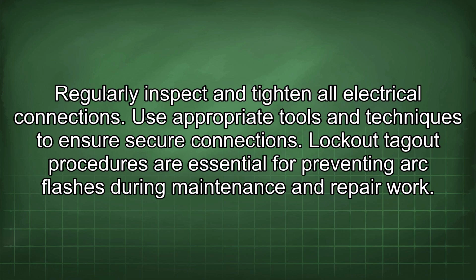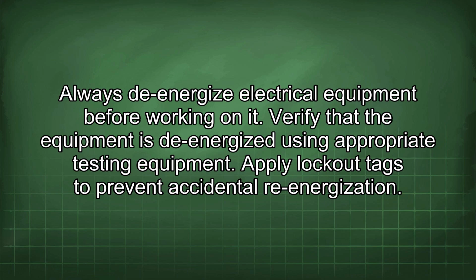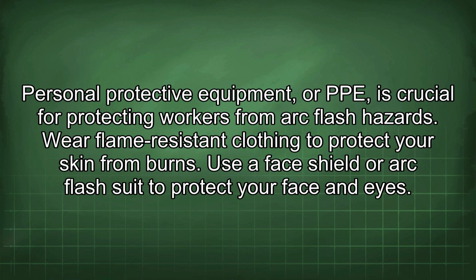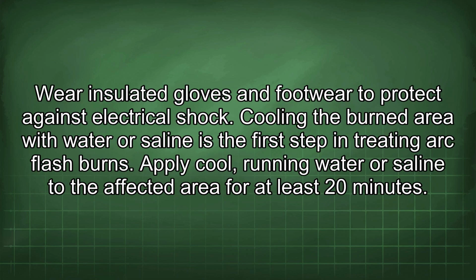Lockout-tagout procedures are essential for preventing arc flashes during maintenance and repair work. Always de-energize electrical equipment before working on it. Verify that the equipment is de-energized using appropriate testing equipment. Apply lockout tags to prevent accidental re-energization. Personal protective equipment, or PPE, is crucial for protecting workers from arc flash hazards. Wear flame-resistant clothing to protect your skin from burns. Use a face shield or arc flash suit to protect your face and eyes. Wear insulated gloves and footwear to protect against electrical shock.